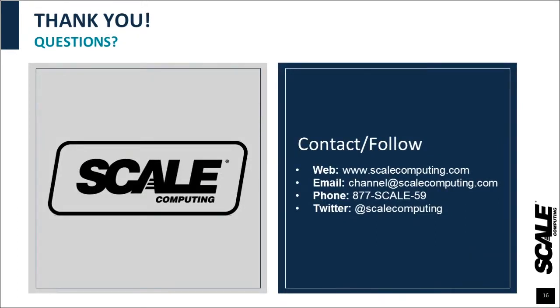Yeah, absolutely. So if you're mix and matching any of the different nodes, you want to take into consideration redundancy. So if you have the 3 HE500 systems to start with, you don't want to add an HE5000 system that is the same capacity as the other 3. But with that said, you'd add them redundantly, maybe add 2 of the larger ones to make sure that they can still function if you have a node failure. The rest of the nodes, you always want to make sure we're N+1 redundant.